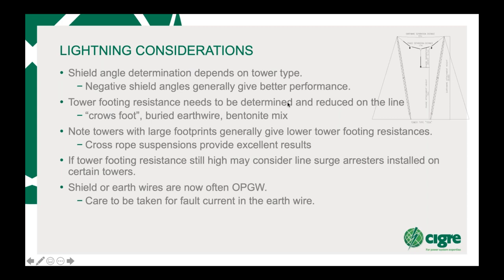The other thing you need to consider is lightning considerations. Now, the shield angle depends on the tower type. This particular tower here, which is an inverted delta, gives you very good lightning protection due to the negative angle of the shield wire to the particular phase. So that's something that you would like to consider. Normally, we'd have a phase out here, which means you've got a positive angle. So if you can have a narrow negative angle, you can actually get very good lightning performance.